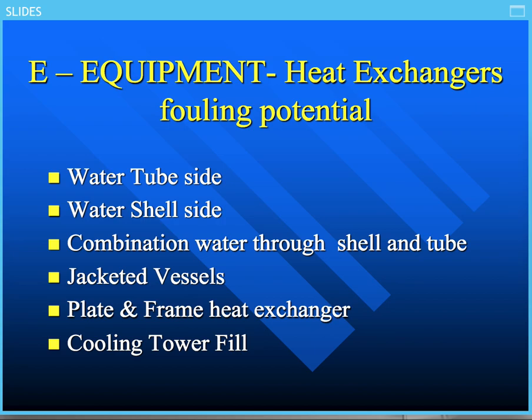And can I have the next slide, please? There's an example of what the fouling can occur in a cooling tower in this fill. And if that is the case, that's going to not only contaminate the rest of the system. Remember, the cooling water is carrying not only your water treatment program to wherever it has to go and protect all that equipment and water contacts, but it also says you can carry some of these problems around, and those problems, of course, can drop out in the heat exchangers and jacketed vessels and what have you.